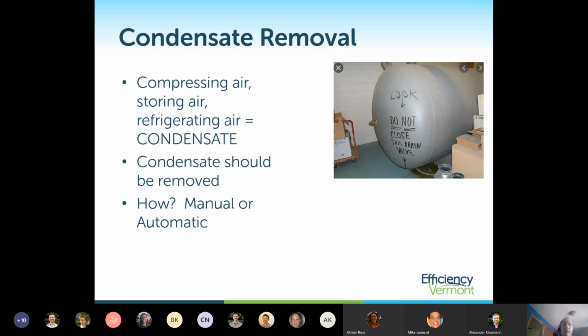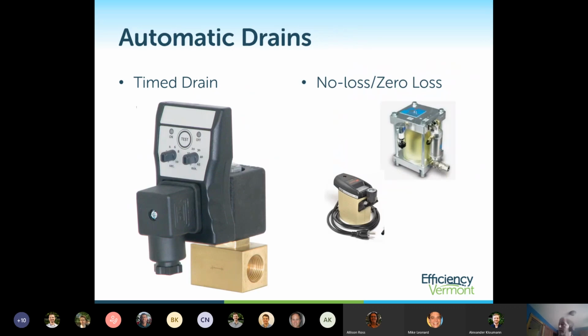I'm not a big person, but I was big enough to be able to just shake the tank a little bit, and it was probably 3/4 full of water. So they've lost a lot of their storage, but also they've been just collecting a lot of water. So you have to get rid of water. And often, for most systems, you will see a drain that is like the one on the left.